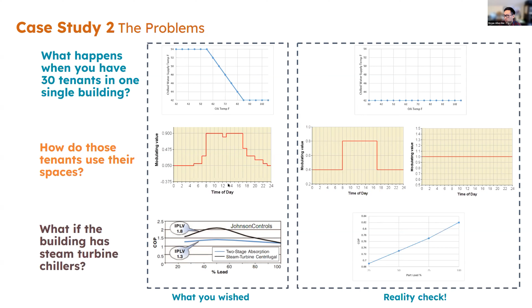So for this project, we're going to get rid of those steam turbine chillers, which are leading to high EUIs. We're going to replace those chillers with magnetic bearing chillers, which are going to have at least a COP of 5.5 to 6, which is very good.